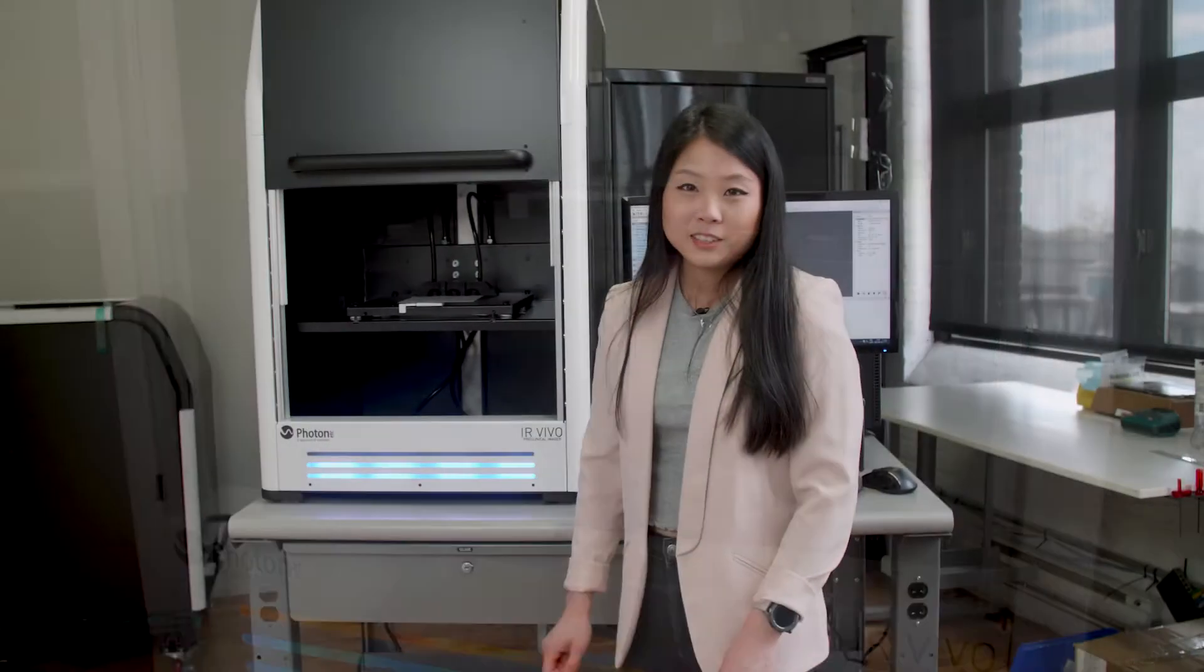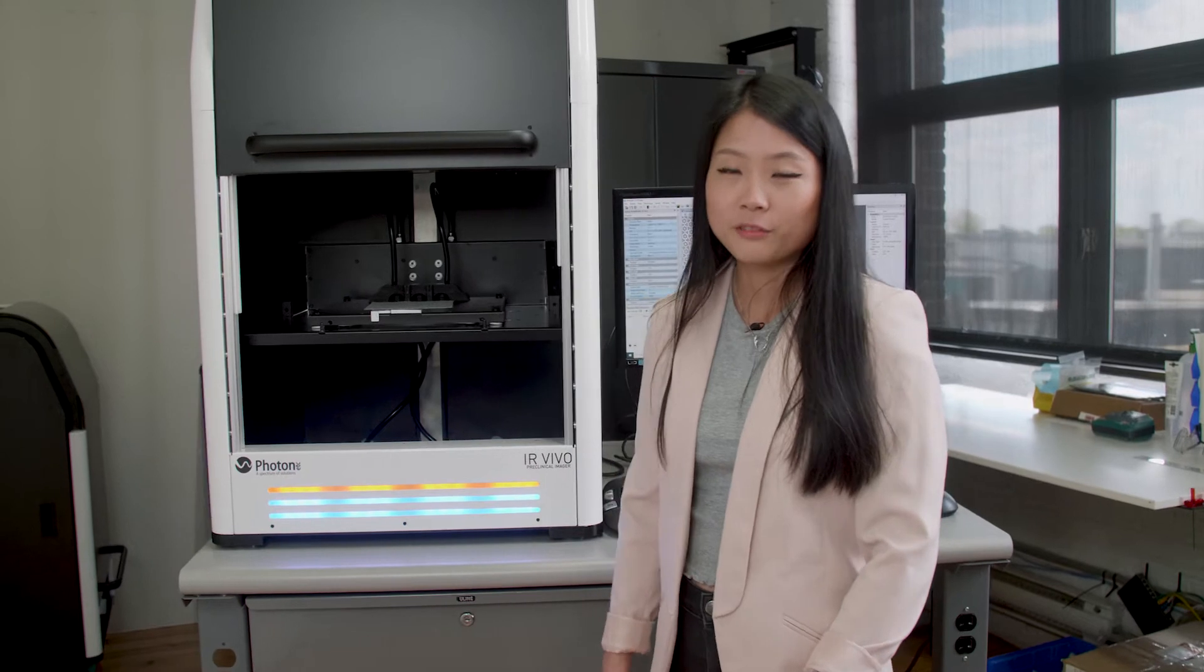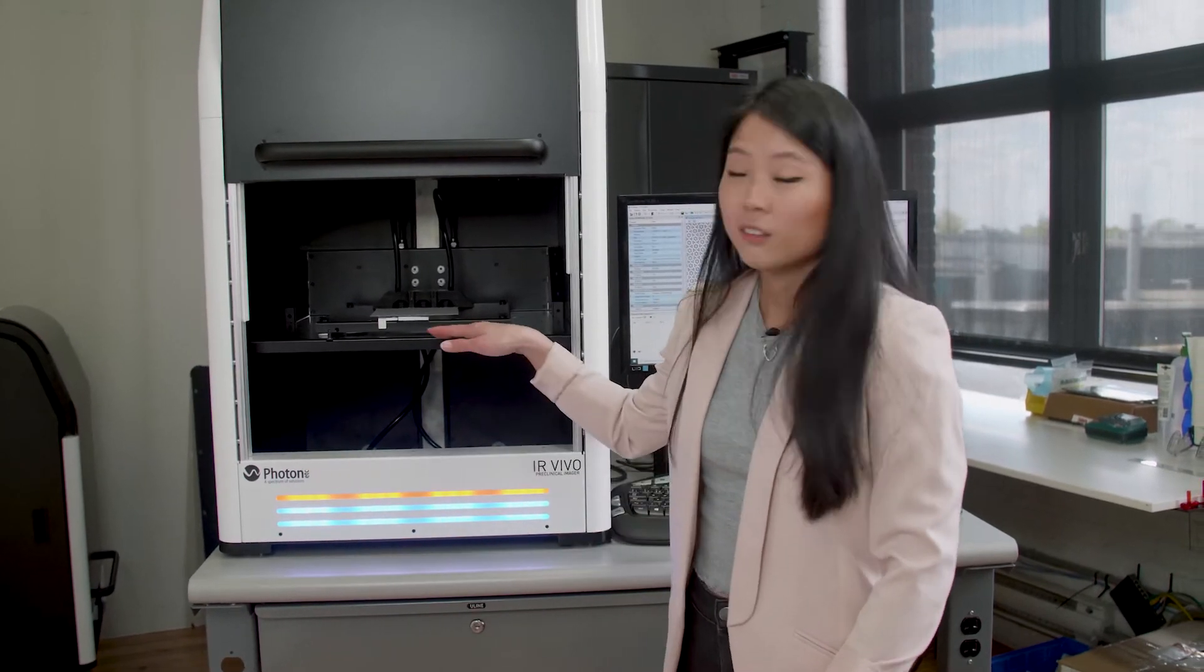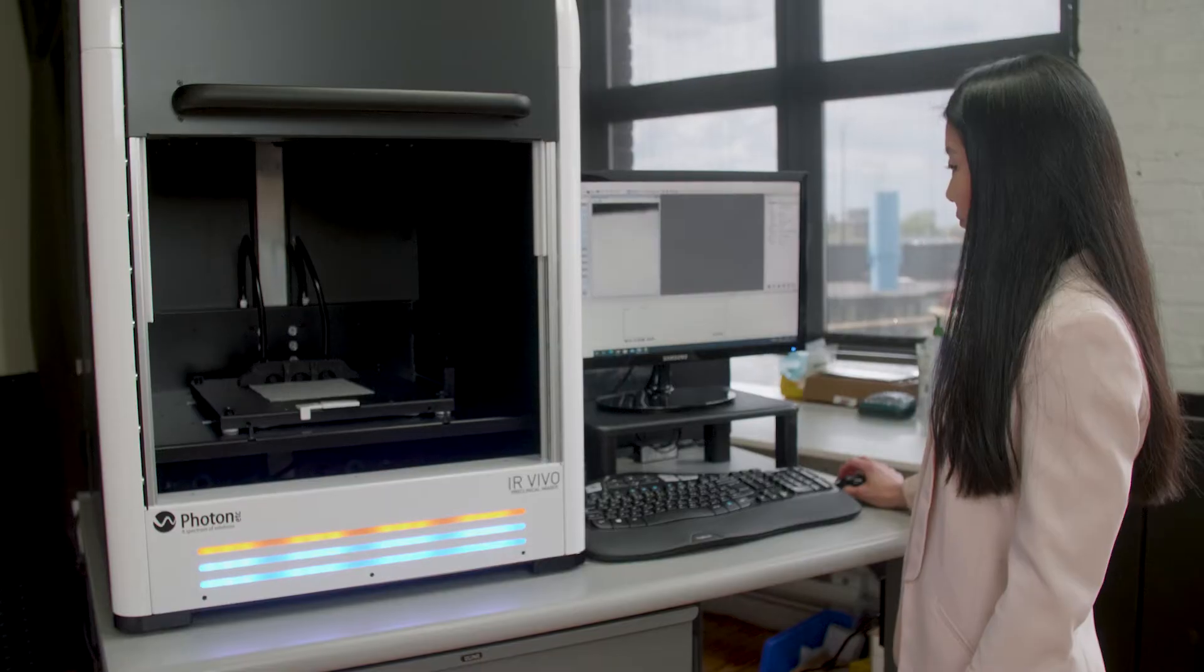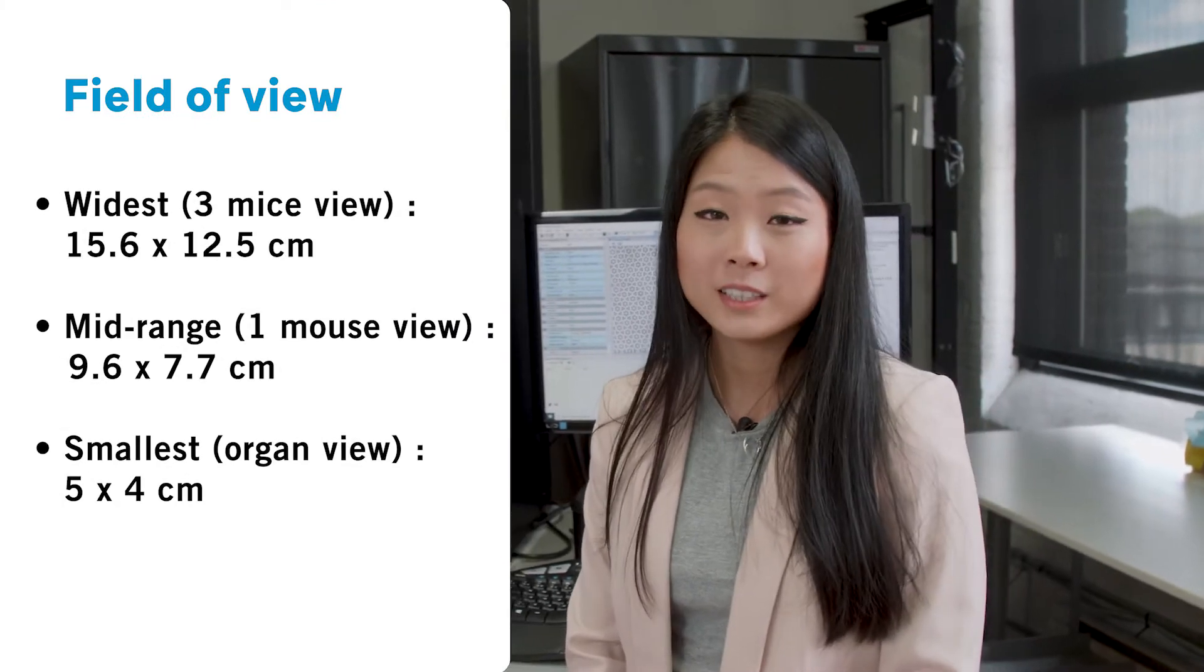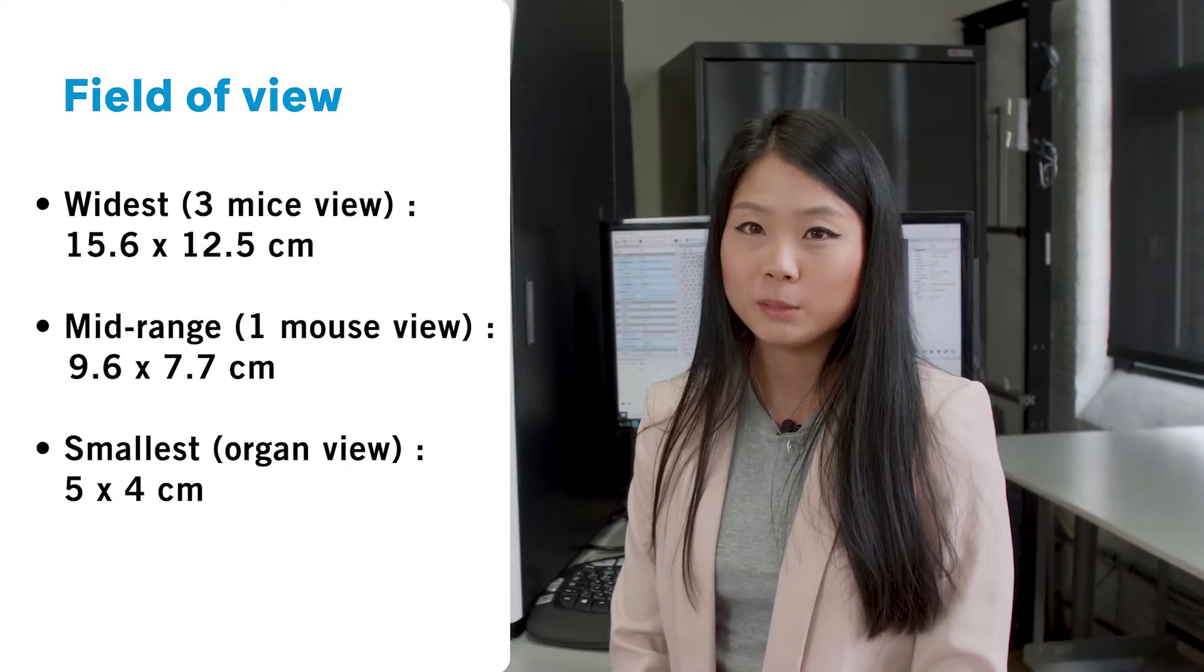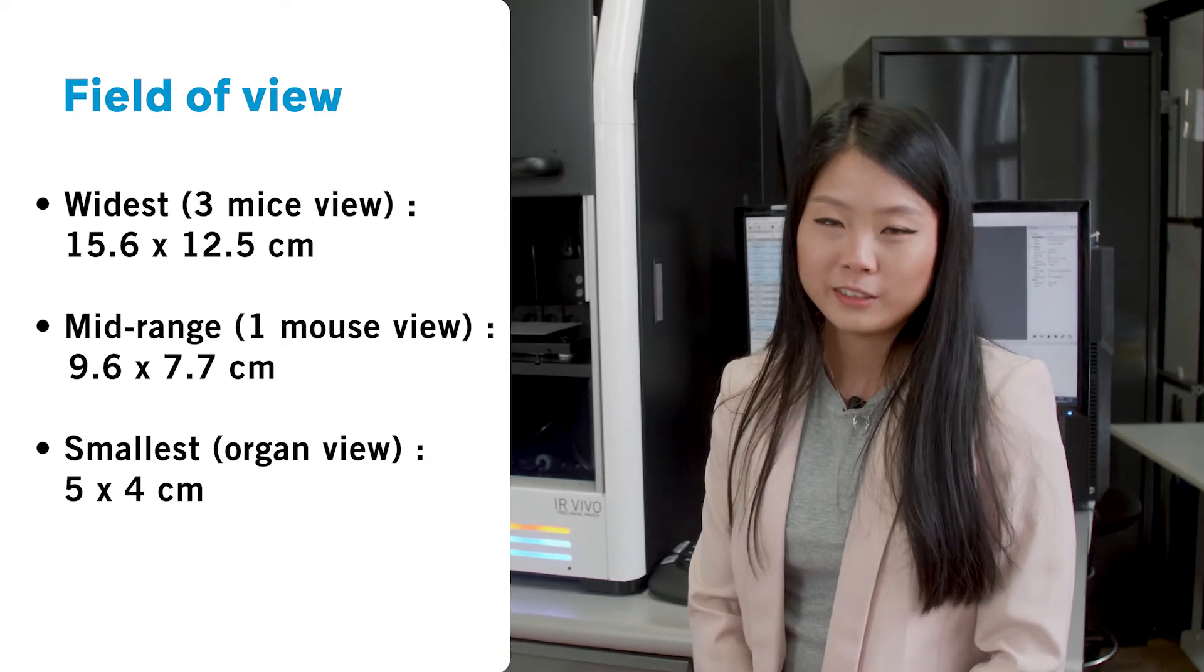We designed the system to be customizable on every part to fit all kinds of needs. For example, the animal stage can be fixed or motorized on the three axes, X, Y and Z. So the widest field of view possible is 15.6 by 12.5 centimeters and the smallest field of view possible is 5 by 4 centimeters.